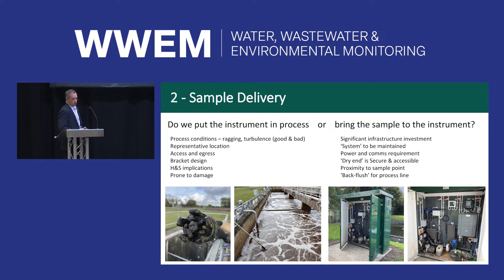On the right, a different way is to take the sample out of the process and bring it to the instrument. We've had sites on final effluent where we didn't have enough depth in the channels or chambers to put the instrument, so we bring the sample out with a peristaltic pump and run it through a kiosk in a safe, clean environment.